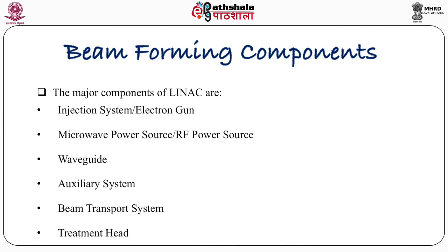The major components of the linac are: injection system, electron gun, microwave power source (RF power source), waveguide, auxiliary system, beam transport system, and treatment head. These are the active parts of the linear accelerator where electrons come out from the electron gun, are injected into the waveguide with microwave power, their energy is increased, and they finally fall on the target to produce photons.